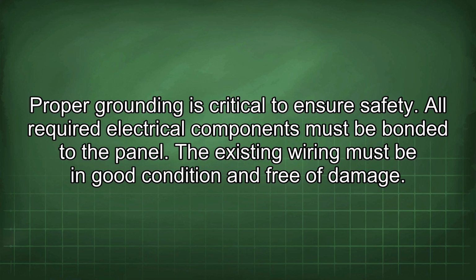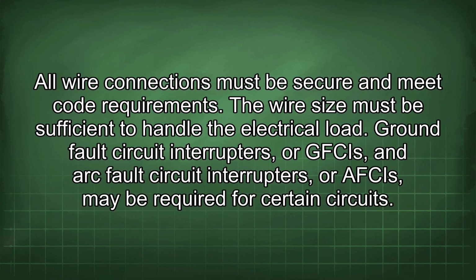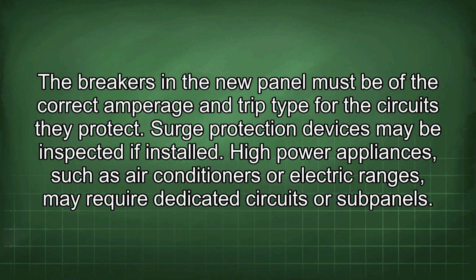The existing wiring must be in good condition and free of damage. All wire connections must be secure and meet code requirements. The wire size must be sufficient to handle the electrical load. Ground fault circuit interrupters, or GFCIs, and arc fault circuit interrupters, or AFCIs, may be required for certain circuits. The breakers in the new panel must be of the correct amperage and trip type for the circuits they protect.